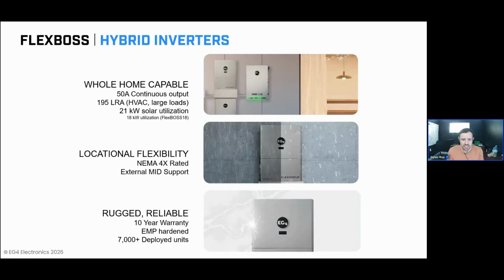Additionally, from a power capability standpoint, the FlexBOSS really enables a host of power sources to be brought in, with solar being kind of the primary one that we see as a means of additional power production within the context of an energy storage system. The FlexBOSS 21 can accept up to 24 kilowatts of solar, and up to 21 kilowatts of that connected solar is actually capable of being utilized by the inverter at any given point in time. And what I mean when I say utilized is the inverter can deliver a 50 amp or 12 kilowatt continuous AC output. However, the balance of available solar up to 21 kilowatts can be made available to charge the batteries at the same time the inverter is outputting power to the home.